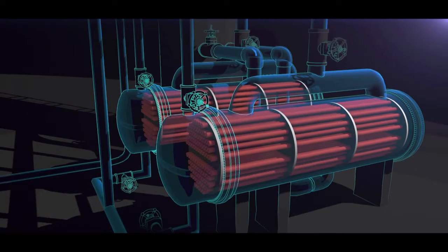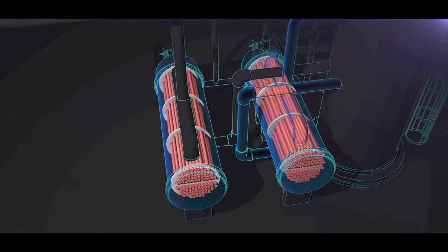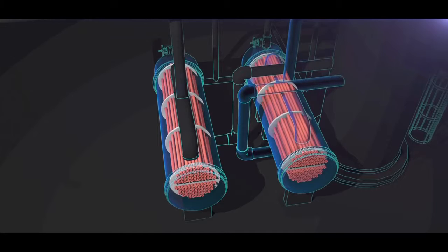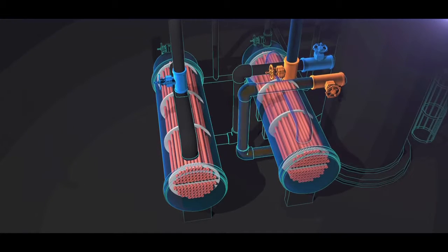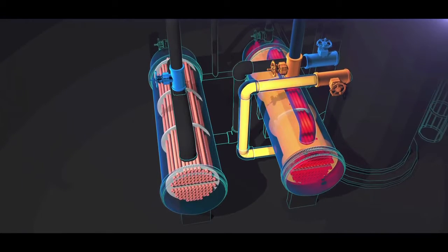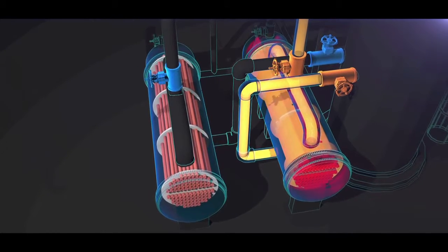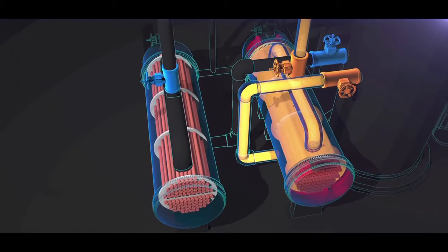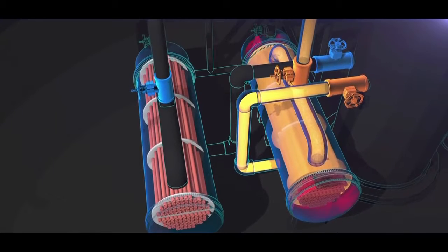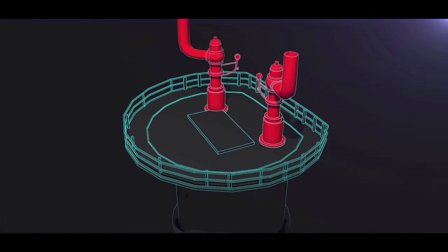To prevent shutdown of the propylene fractionator each time the reboilers needed to be cleaned, in 2001, new valves were installed on each reboiler to allow for operation of only one at a time. The other reboiler is on standby, clean and ready for use. But unforeseen at the time, these valves introduced a serious hazard. They isolated the standby reboiler from its protective pressure relief valve, located on top of the fractionator.